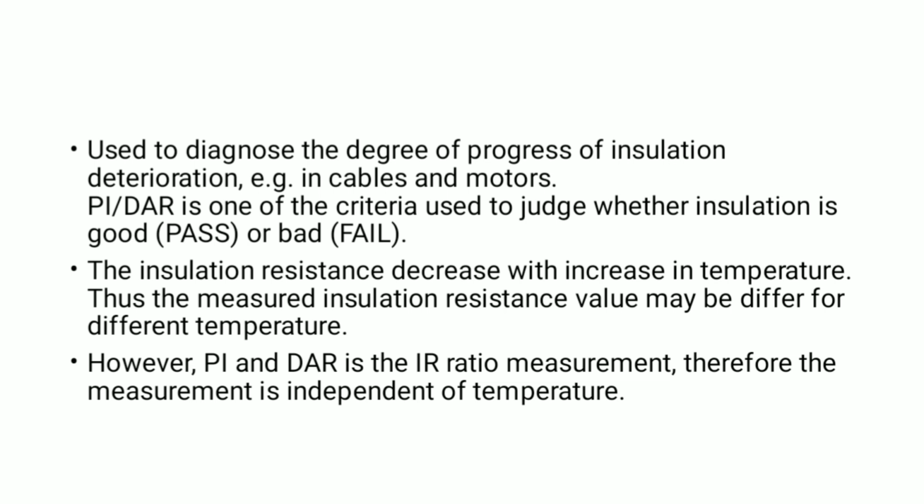Yes, we get an idea from the insulation resistance, but if you take the insulation resistance in the summer season, it gives you a different value than in the winter season. So DAR and PI tests are used to diagnose the degree of progress of insulation deterioration in the cables and the motors. Insulation resistance decreases with increase in temperature, and thus the measured insulation resistance value may differ for different temperatures. PI and DAR are IR ratio measurements, therefore the measurement is independent of temperature.